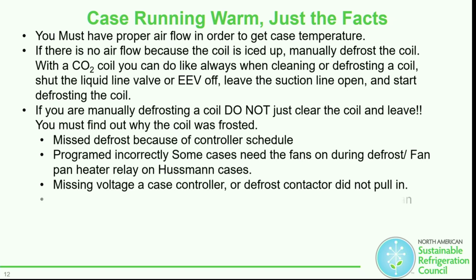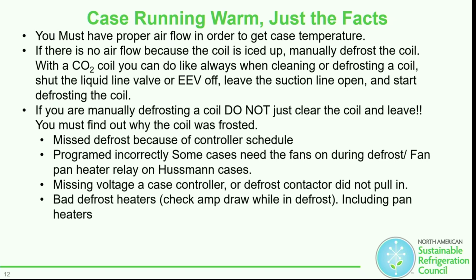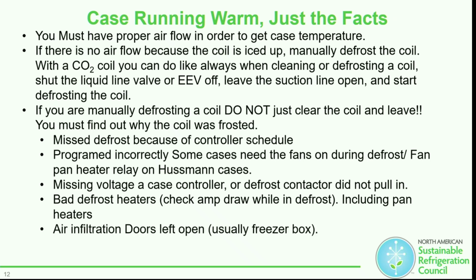Defrost contactor did not pull in, maybe. Bad defrost heaters: check the amp draw while it's in defrost, including the pan heaters. Like I said, check it, but then check it again and check it again. Because if you just check it the first time, you're like, well, it was on. Well, maybe it was only on for 5 minutes and then you missed why it pulled out, right? Air infiltration, doors left open, usually in a freezer box. Other reasons why that thing might ice up.